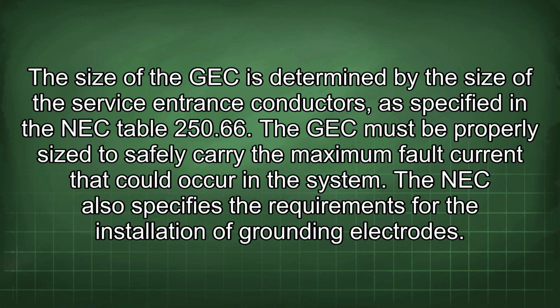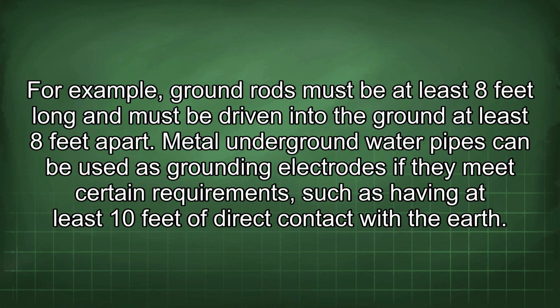The NEC also specifies the requirements for the installation of grounding electrodes. For example, ground rods must be at least 8 feet long and must be driven into the ground at least 8 feet apart. Metal underground water pipes can be used as grounding electrodes if they meet certain requirements, such as having at least 10 feet of direct contact with the earth.